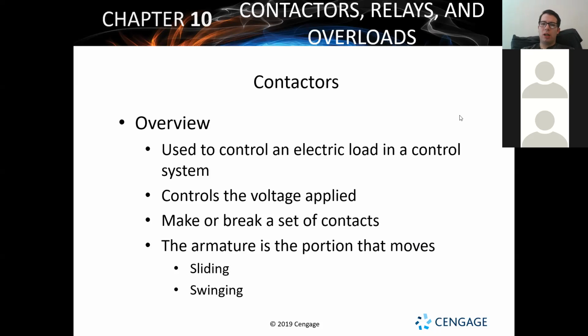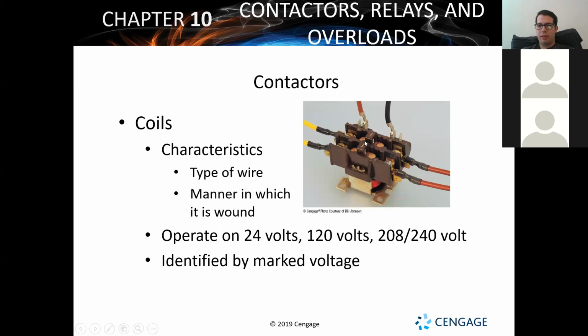Now, typically for your contactor, that's your armature right there in the middle. Contacts are all these connections right here on these sides. Now, the ones that aren't your contacts are these two leads coming in over on this side. They are part of your contactor, but they're not your contacts though. These are your connections to your contactor coil, this guy right here at the bottom.